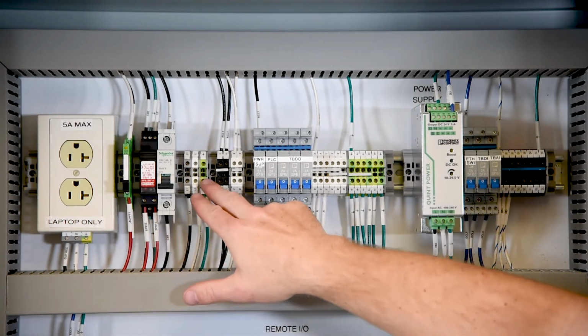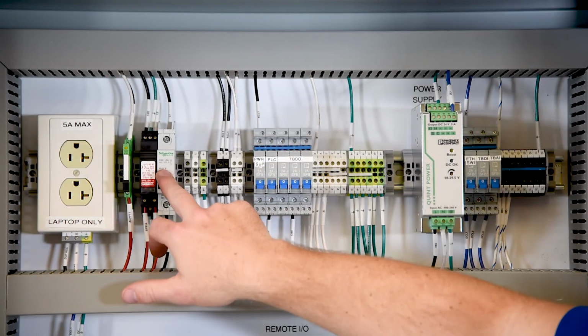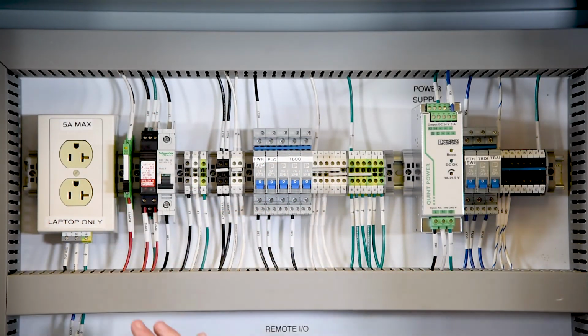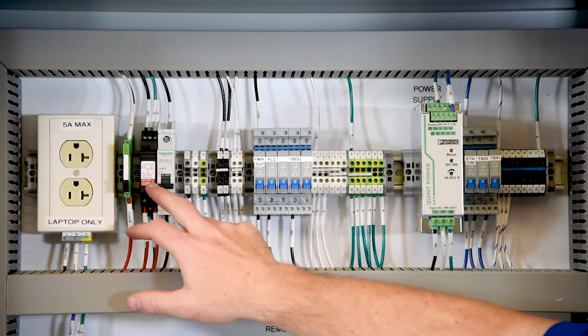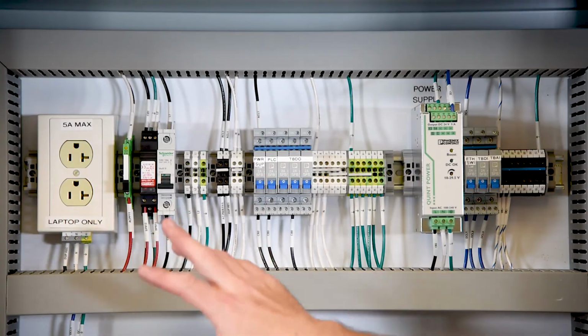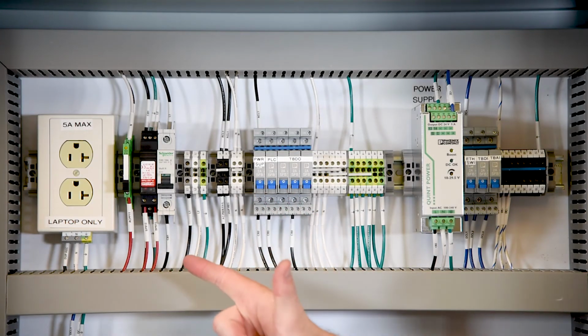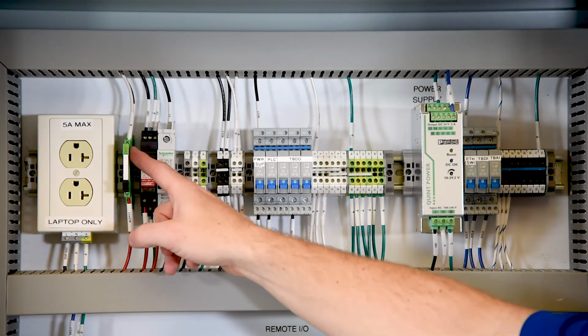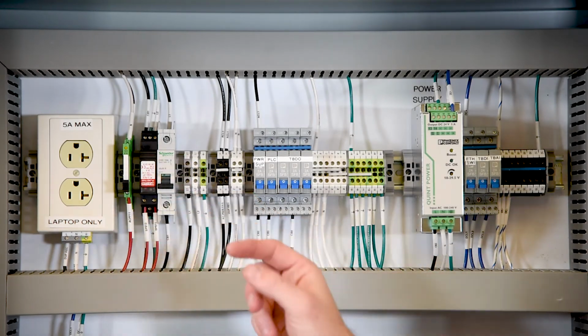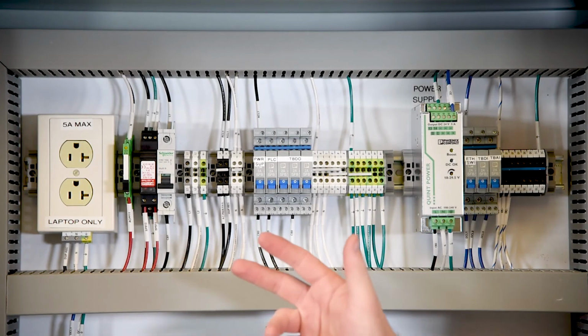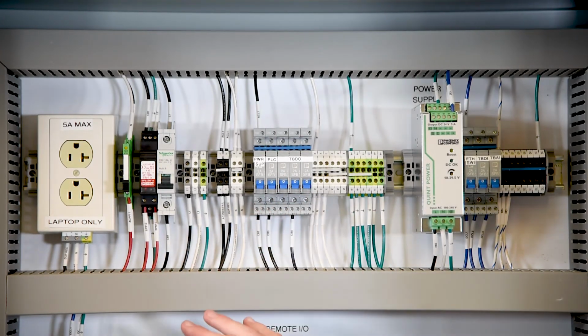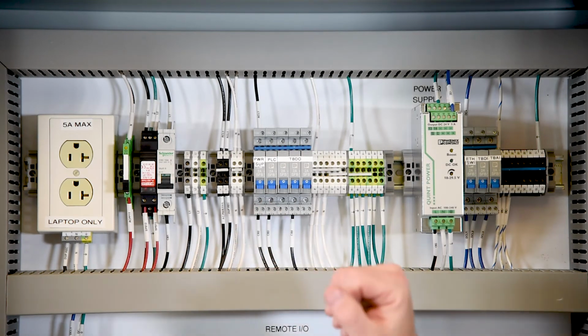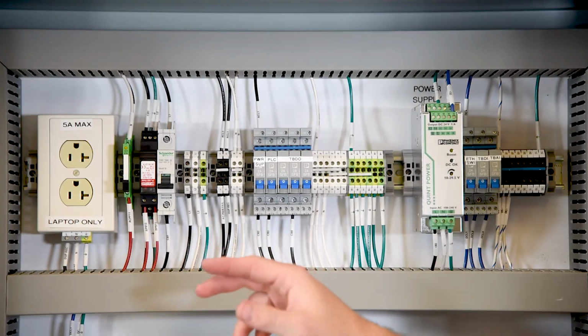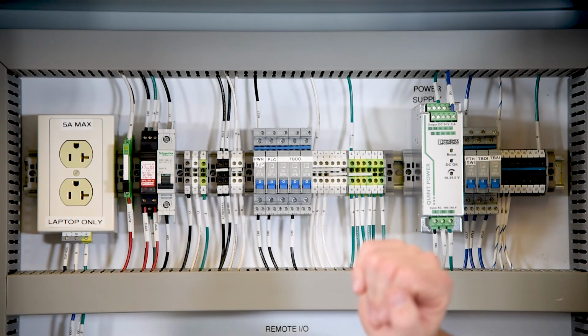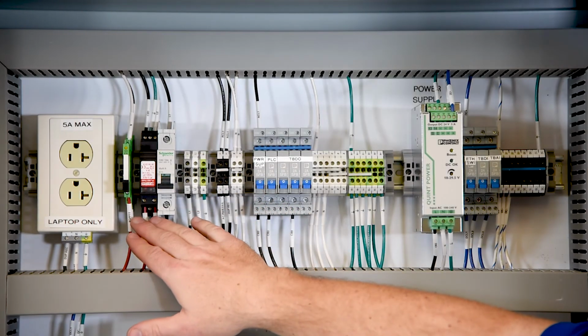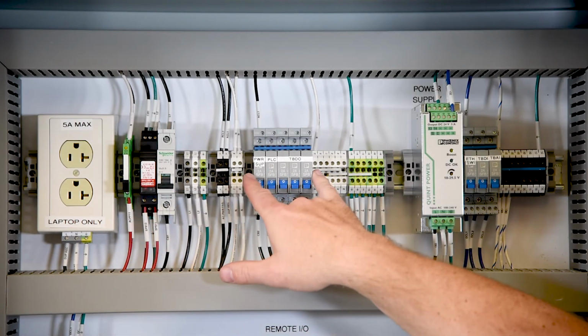From the main input power, we then run to the protection on our panel. We have a main circuit breaker, which will kill power to all the devices within the panel itself. We also have a surge protector, which will protect all the devices within the panel in the case of a power surge or a lightning strike. You can see here we also have the AC power fail relay. Again, this monitors the input power and sends a message in case of a power loss or power failure to our PLC notifying us that we no longer have power. Keep in mind, the AC power fail can only function if we have a UPS operating within the panel as well. Next, we take our power from the protection over to our supplementary breakers.